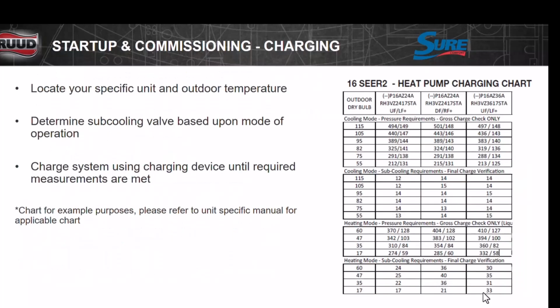On the outdoor unit is a chart called a charging chart, okay? It's going to give you the target subcool that you need to run with that matchup. One of the things you have to pay attention to is, as you can see on this unit, this is a 2-ton unit. It has a UF, an LF, a DF, and an RF. All right? This means upflow. This means left flow. This means downflow. And this means right flow.